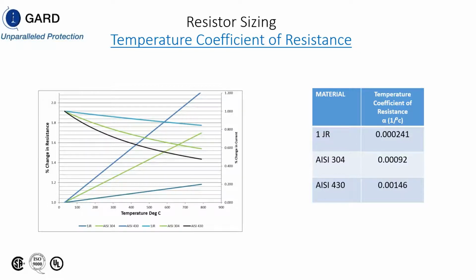resistance change that you can have in the resistor during the 10-second rating, specifically for a 10-second rated resistor, because the resistor is allowed to go to 760 degrees C above ambient. When that happens, fundamentally, you change the value of resistance of the resistor, and it's going to increase. And when it increases too much, you decrease the fault current. So CSA says you can't have the current less than 80% of the let-through current, which basically means you can't increase the resistance by more than 25%.